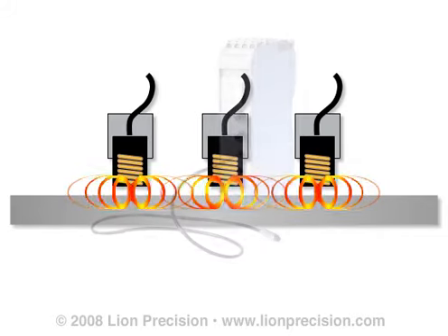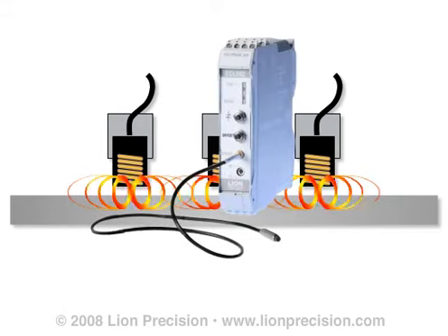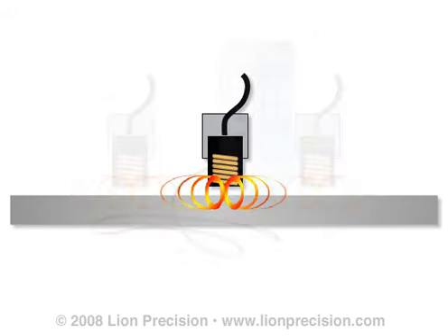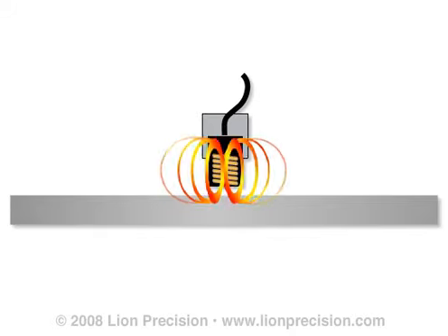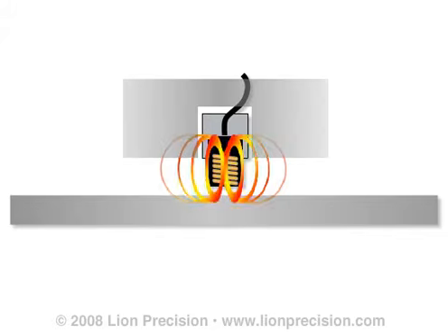If this type of mounting is unavoidable, sensors based on digital technology, such as the ECL202, can be specially calibrated to reduce or eliminate the interference from adjacent probes. The magnetic field from an eddy current probe also extends about 1.5 diameters behind the probe. Any metallic objects in this area, usually mounting hardware, will interact with the field and affect the sensor output. If nearby mounting hardware is unavoidable, sensors can be calibrated with the mounting hardware in place, which will compensate for the effect of the hardware.